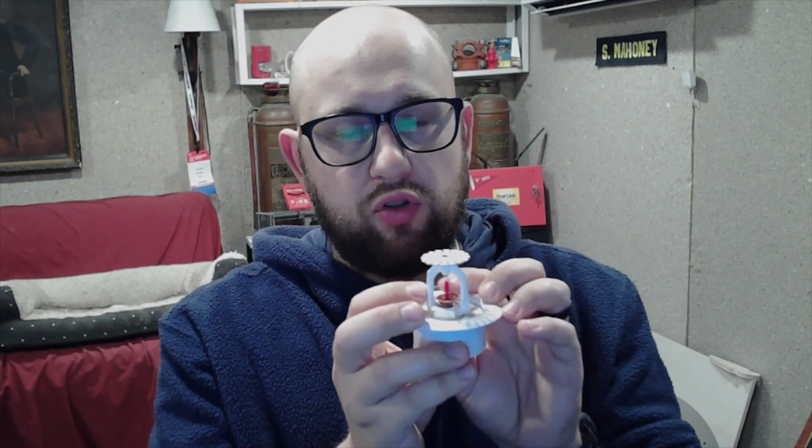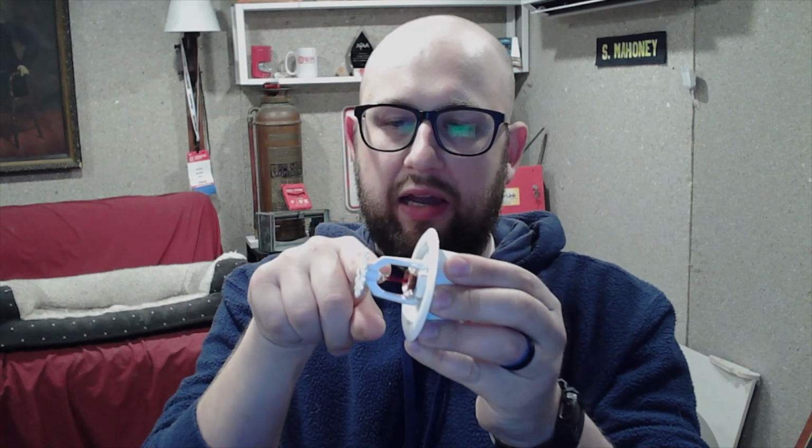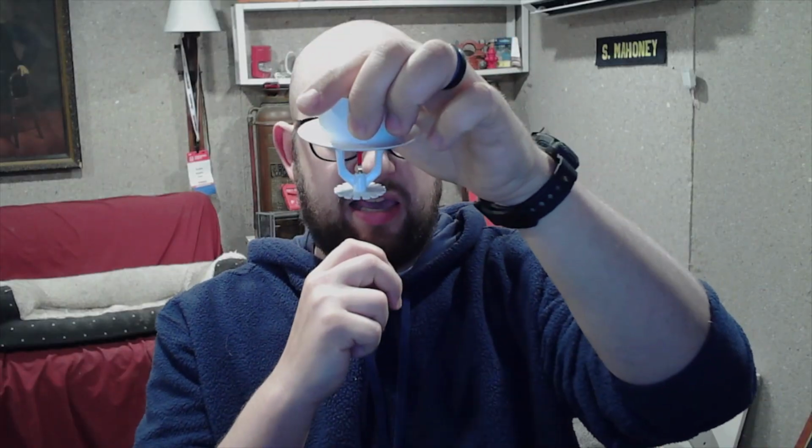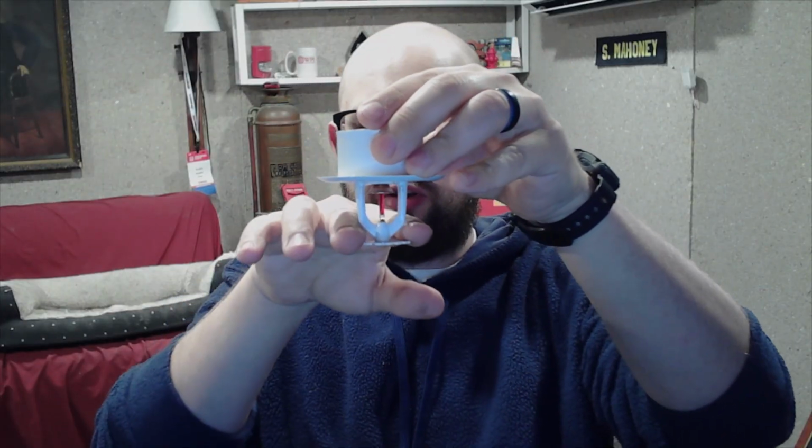This example is a red fusible element, which means it's going to activate at 155 degrees Fahrenheit. Once that activates, the cap and seal are going to come away. The water is going to spray against the frame arm and then onto the deflector. And the deflector is what's going to create our spray pattern. In this case, we've got a pendant sprinkler. It's going to create a spray pattern out and then cover the floor.